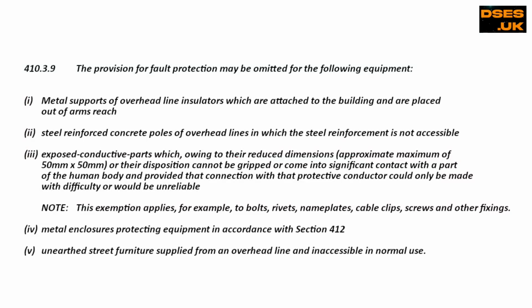Not necessarily, because Regulation 410.3.9 allows fault protection to be omitted for exposed conductive parts with reduced dimensions, a maximum of 50 by 50 millimetres, or where their disposition is such that they cannot be gripped or come into significant contact with a part of the human body.